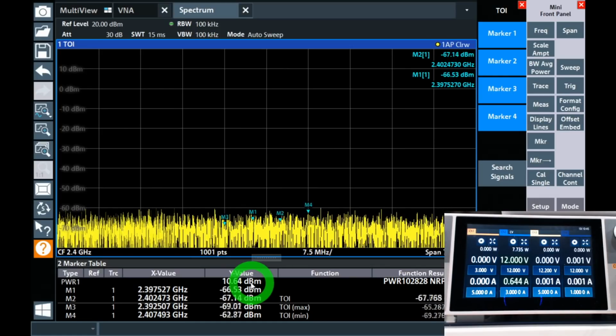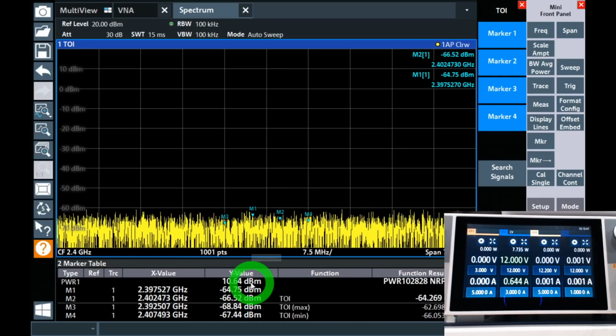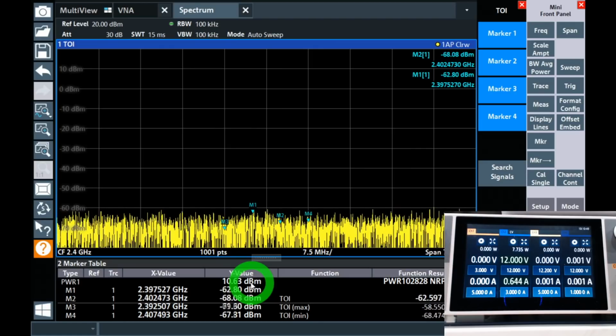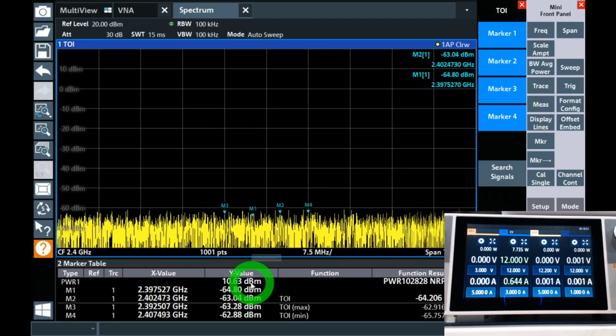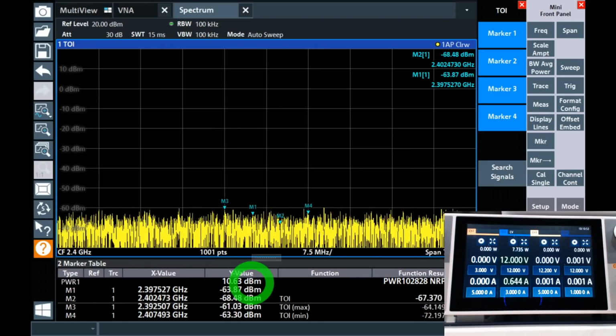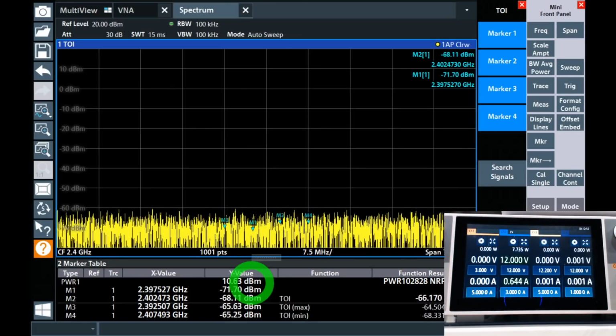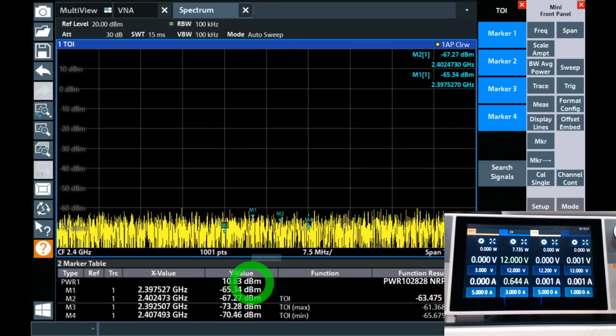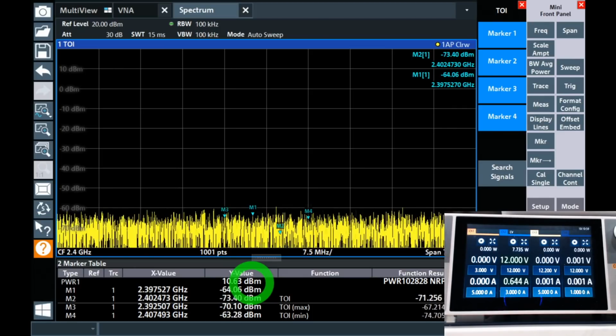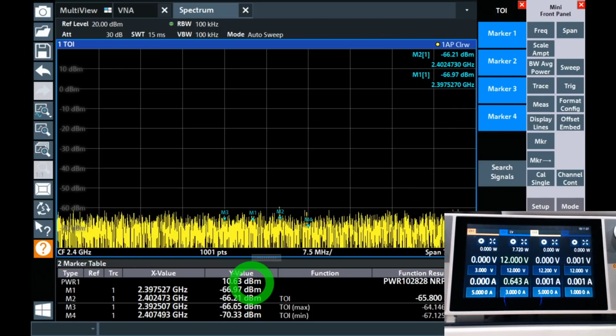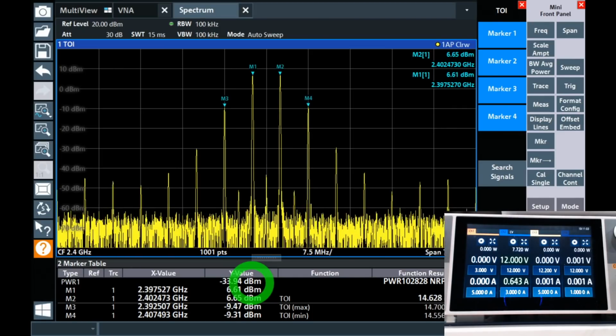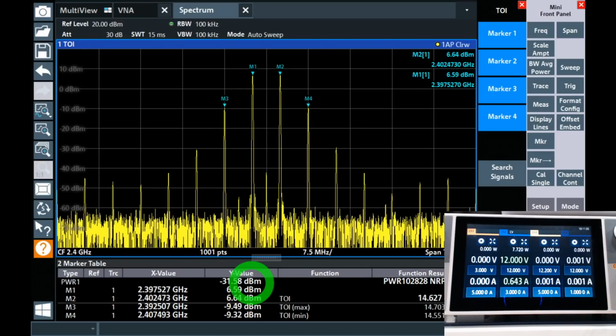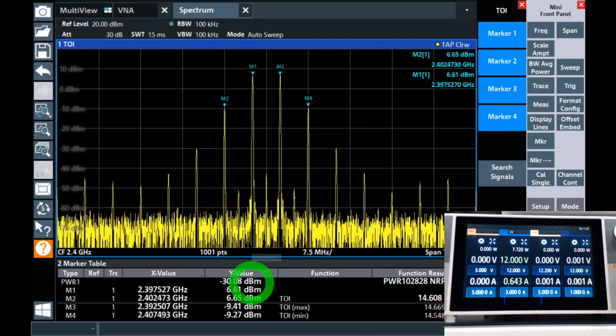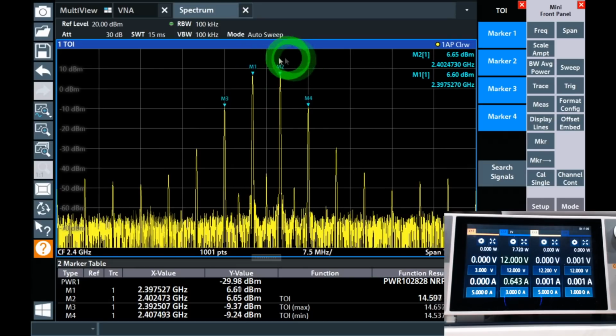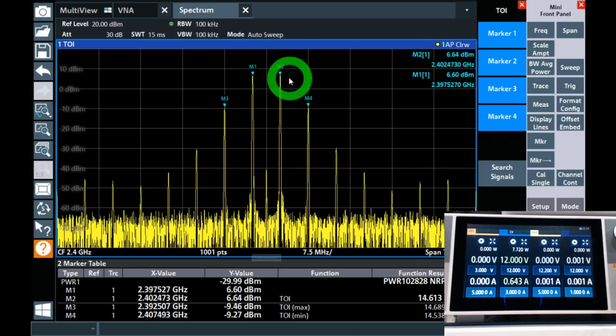That's the total power. We add 20 to that, we are over 30 dBm, exactly what we were expecting. Now, this is not a constant tone signal. This is a two-tone signal, and it's being integrated across all the frequency. Let me switch it back again so you can see the difference to port 2. There we go. You can see the individual tones are, of course, smaller. You can see the power of the individual tones is not 10 dBm. That's to be expected because it's doing the integration.